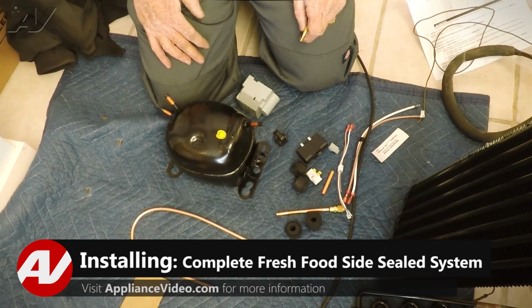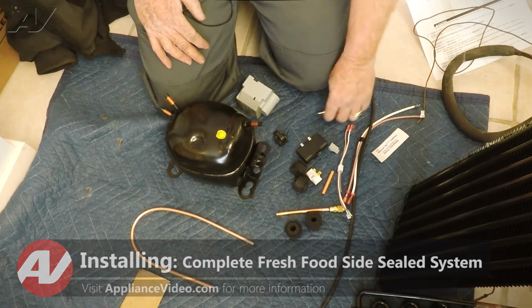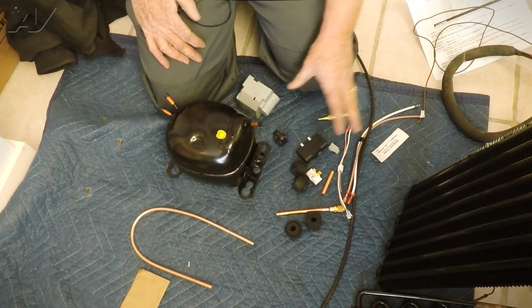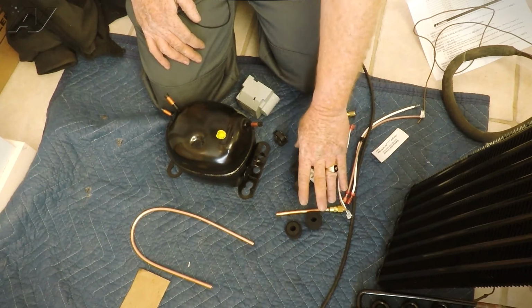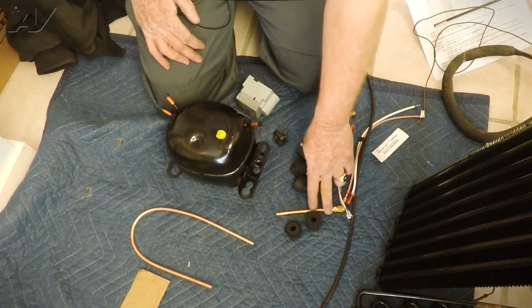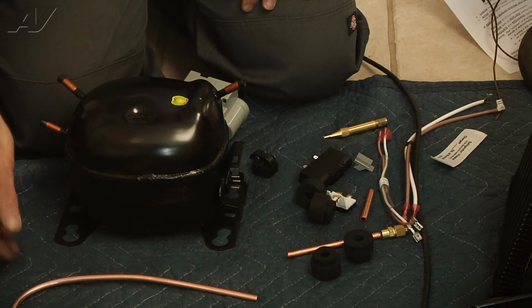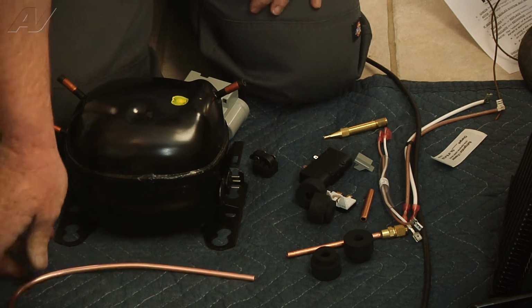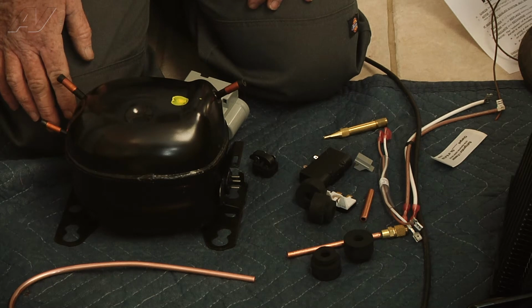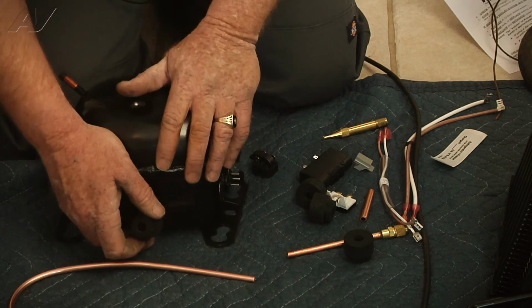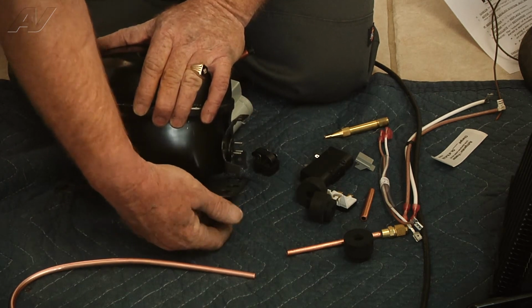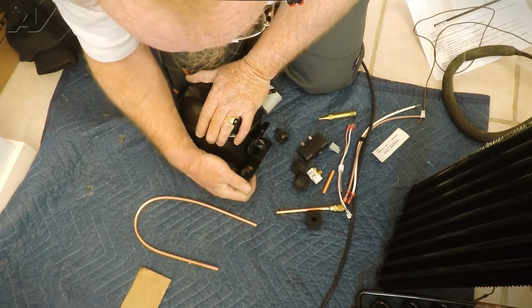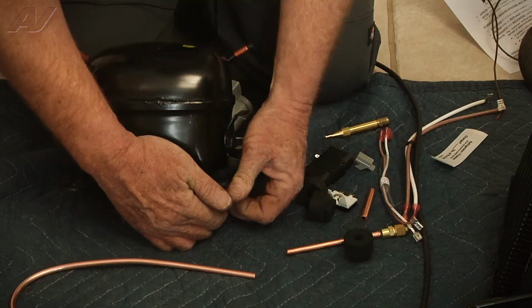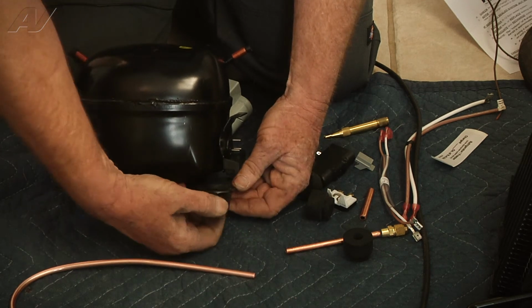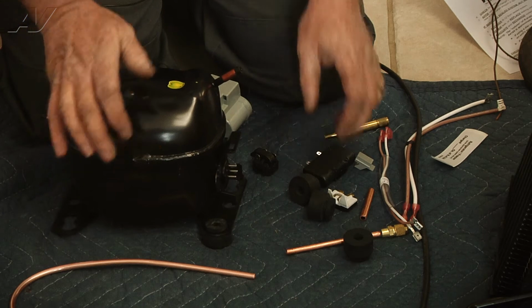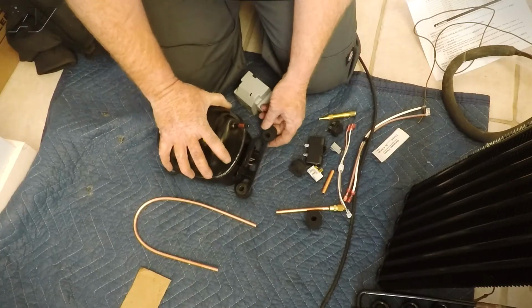Now, before we can install the compressor, we have some prep work we want to do on it. The compressor kit comes with wiring, start device, grommets for the mounting plates, access valve for the compressor, and also this connecting tubing like the old compressor had for the high side. So what we're going to do first is the grommets. We're going to tilt the compressor and press the grommet into the hole, and then we're just going to twist it a little bit and let it seat, and repeat that process all the way around.